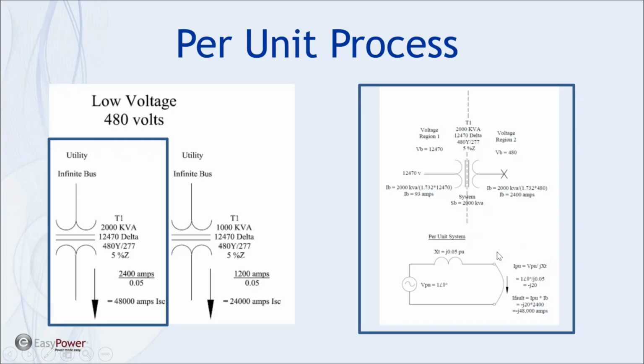So we put a short circuit here on the end of it, and my calculations down here give the actual per unit fault current that's going to flow, which is my applied voltage divided by my resulting per unit impedance. So it's 1 angle 0 degrees divided by J, and I make all my inductive reactances positive J. I've also seen folks apply a voltage at 90 degrees, and there are a couple of different ways you can do it. This is just my system, but inductive reactances are always positive J, and capacitive reactances are always minus J in my approach.